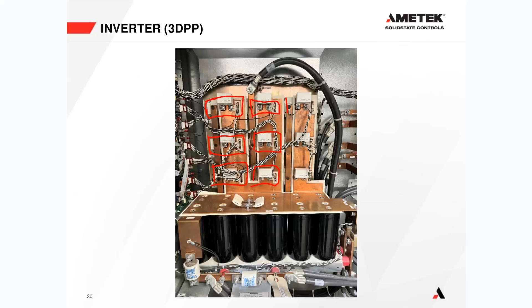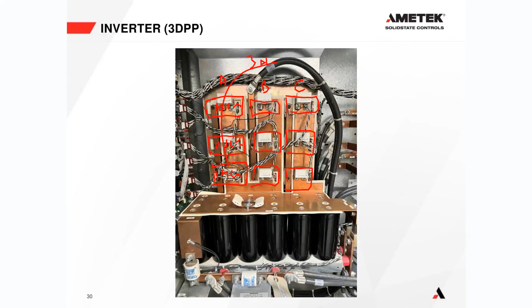Basically the way our systems work is for 10 kVA, we'll use one IGBT, and for every 10 kVA above that, we put another IGBT pack in parallel. So let's say this is A phase, B phase, C phase - that's 10 kVA, 10 kVA, and 10 kVA, so we get 30 kVA out of this system.